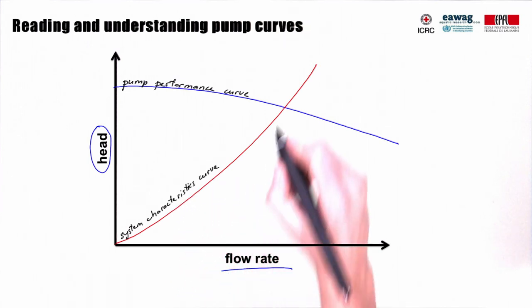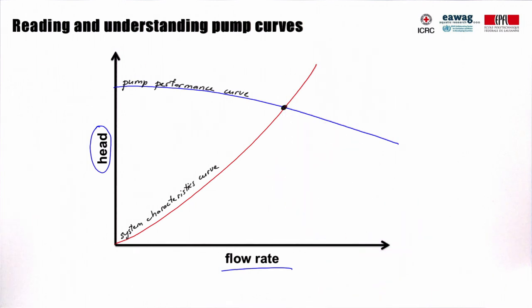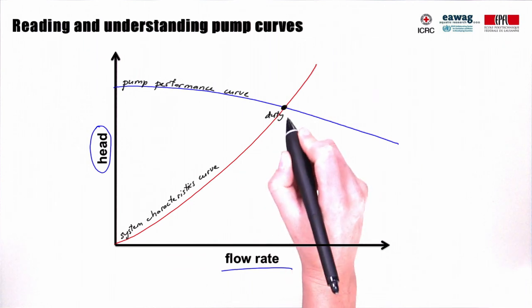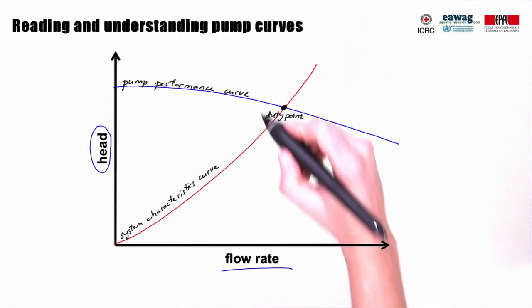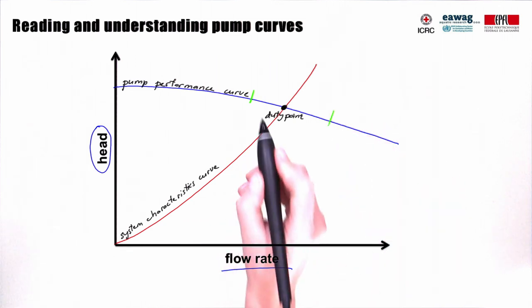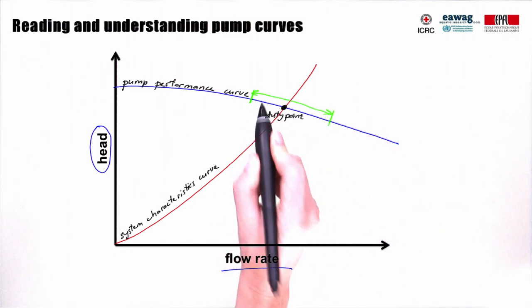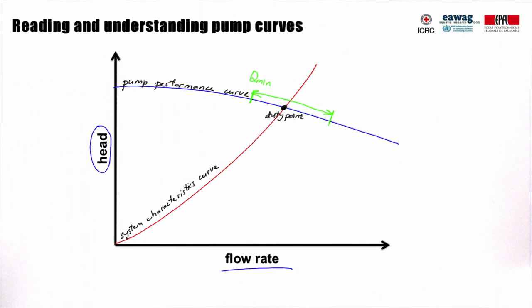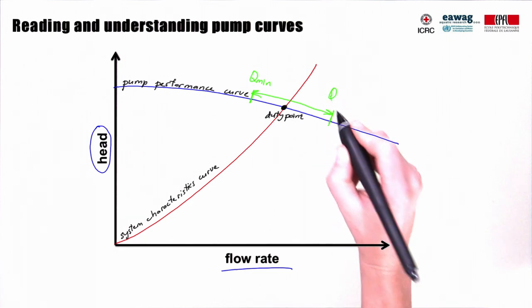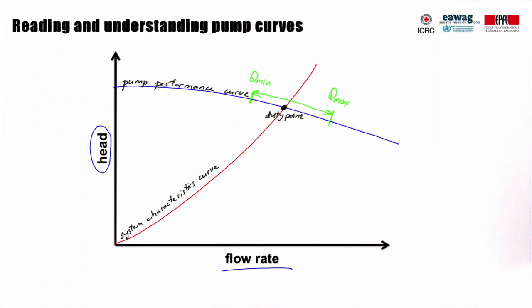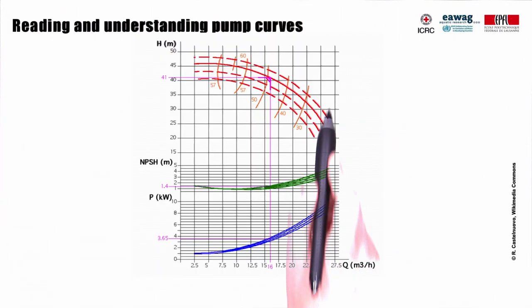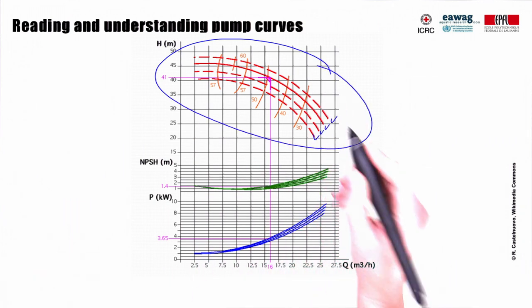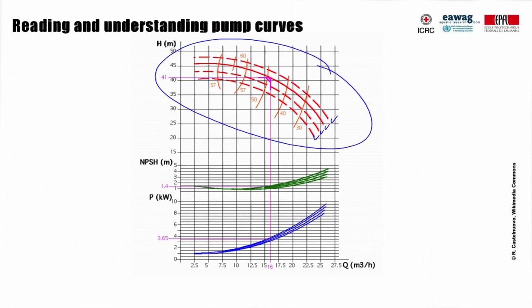The point where the pump performance curve and system characteristics curve intersect is called the pump operating point or duty point. At the duty point, there is a balance between the system demands and what the pump can deliver. For each pump, the manufacturer will define the allowable pump operating range, indicating the values of minimum and maximum flow rate. The operating point of the pump needs to be within the operating range to provide trouble-free operation. For centrifugal pumps, multiple curves can be shown on the pump curve, indicating the performance of the pump at different impeller diameters. Impellers can be trimmed to match the head and flow needed in the application within the given range.